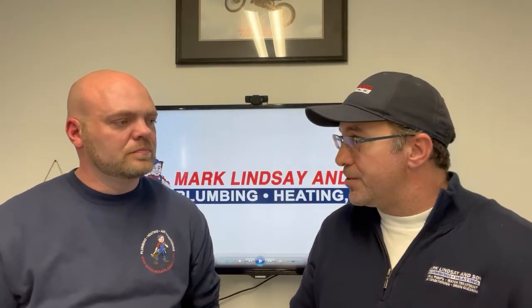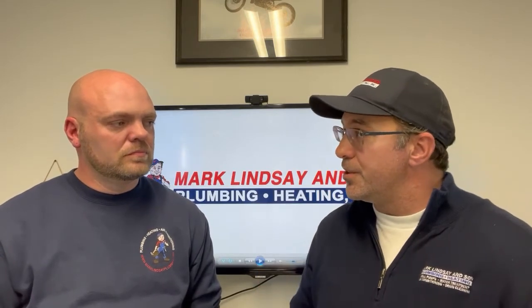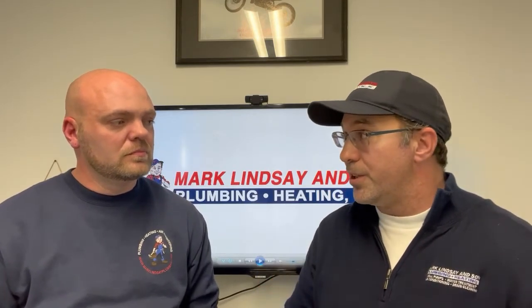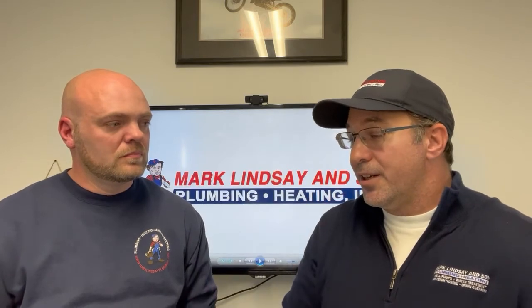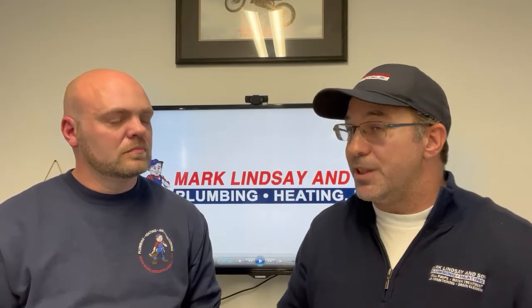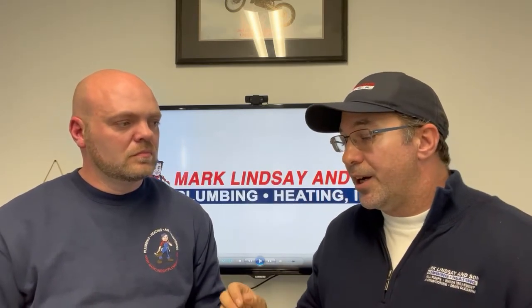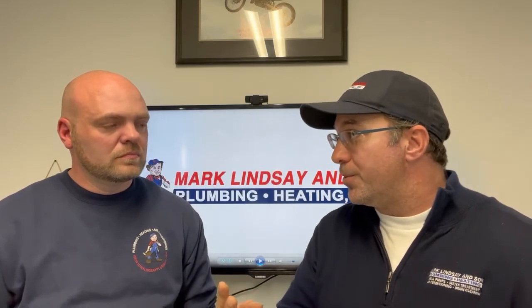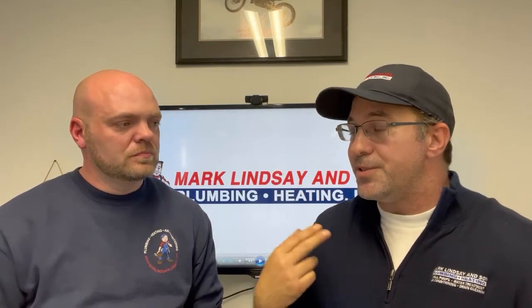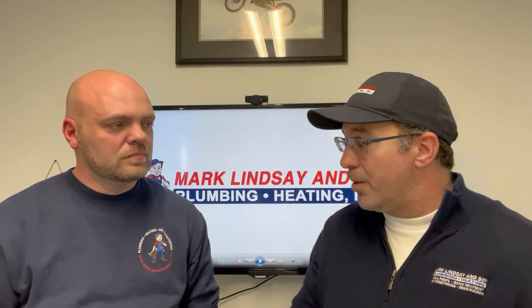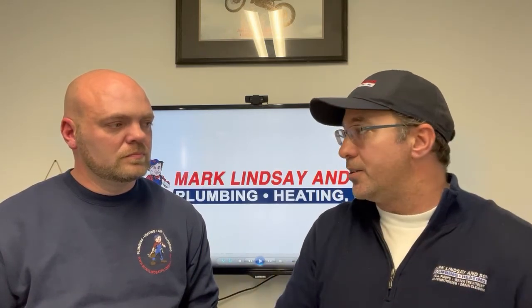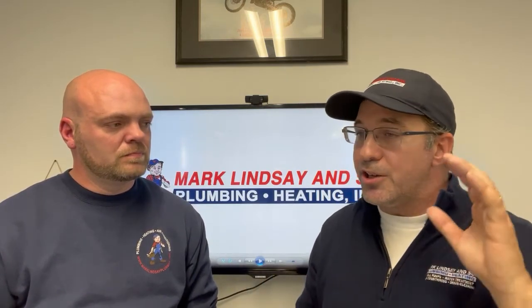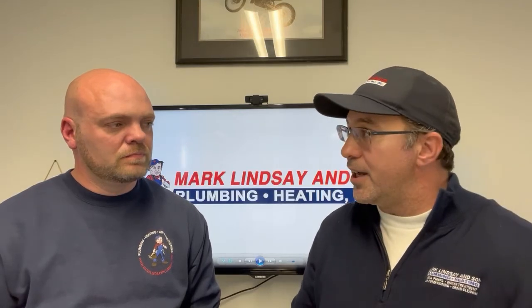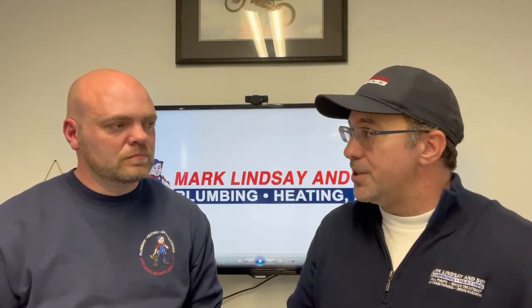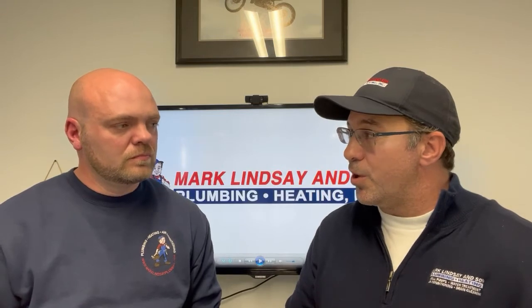Now ice happens, systems freeze up for one of two reasons, Dave, and it's always one of two reasons. There's no reason outside of it. The first reason is lack of refrigerant, which means they have a leak in the system. The second reason is lack of airflow, and probably the most misdiagnosed problem that any consumer out there, any homeowner has out there when they call an HVAC technician out to the house. One of the most misdiagnosed problems is improper airflow.